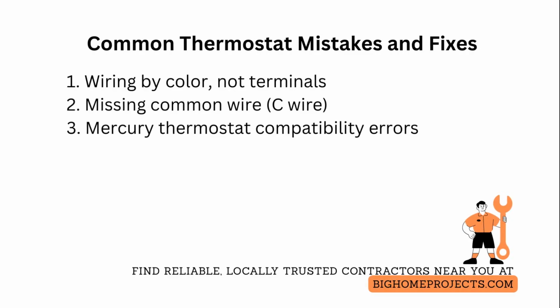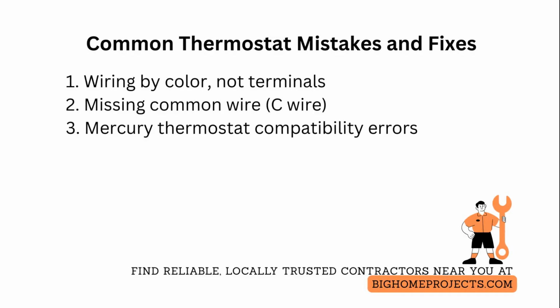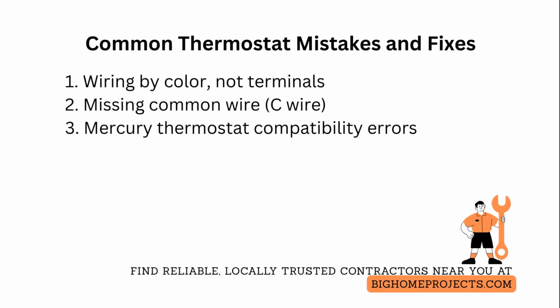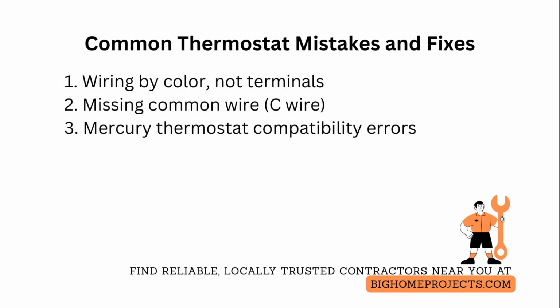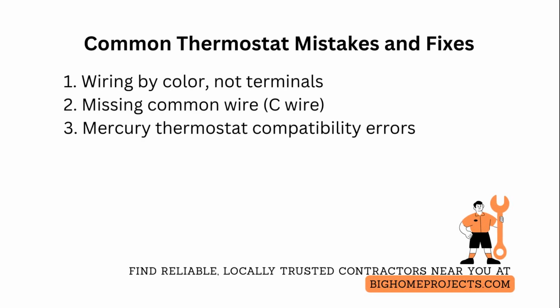One of the top issues is missing common wire or C wire problems that lead to rechargeable battery drain or intermittent restarts. Fix by installing a common wire from the air handler, using a 24-volt plug-in power adapter, or choosing a battery-only thermostat designed for low-power operation.